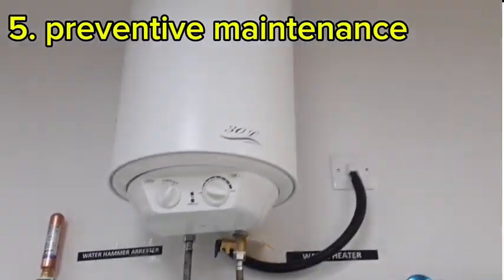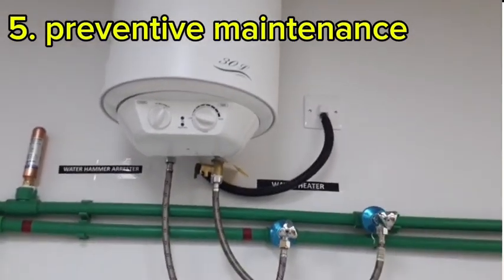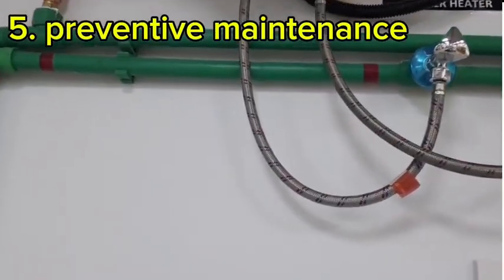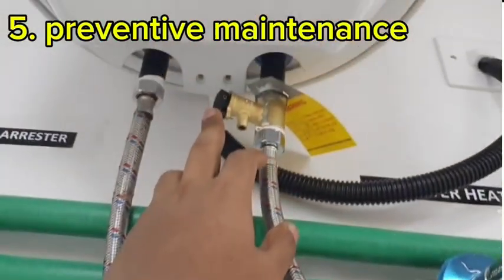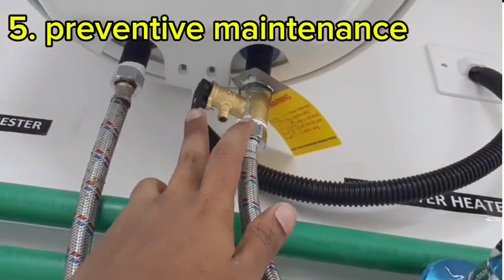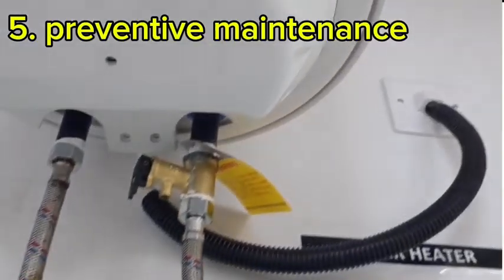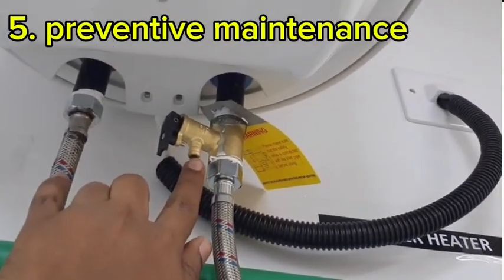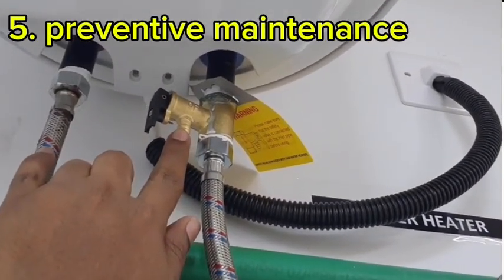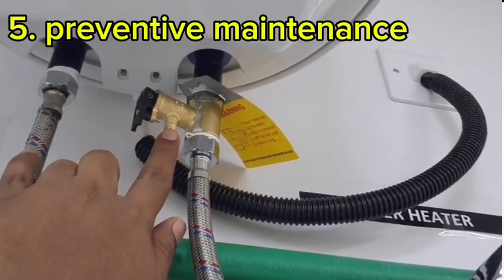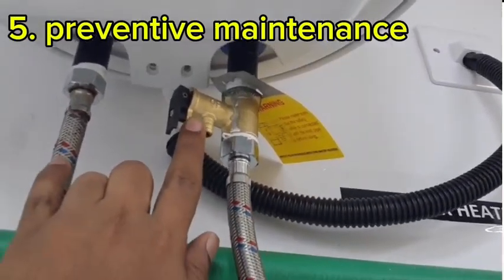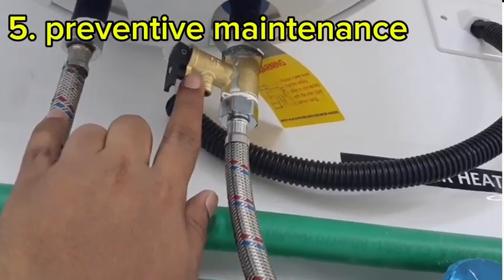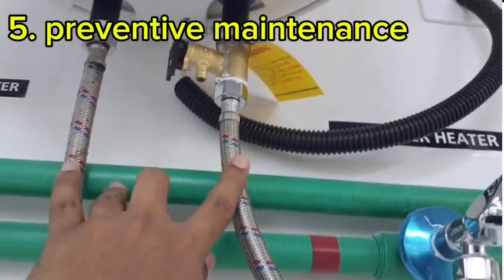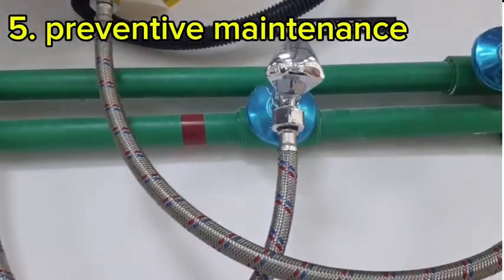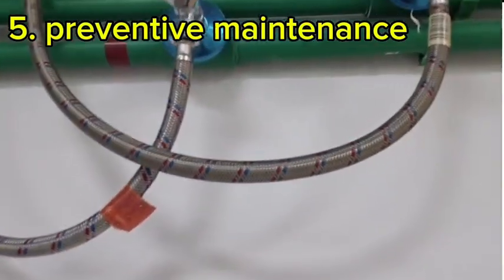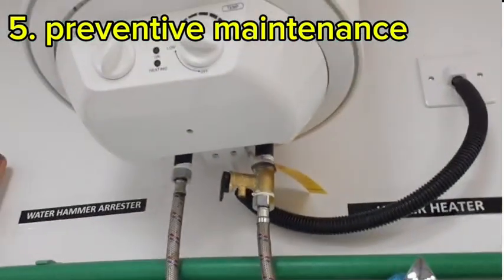And the last part of the video is how to carry out preventive maintenance. This is the most important thing while you conduct preventive maintenance: open this valve and release the air from the water at regular intervals during all preventive maintenance. You have to make sure that the safety valve is connected in the inlet pipe before using. Then you have to check all the electrical connections. You have to ensure there is no leakage. Check the water heater physically.